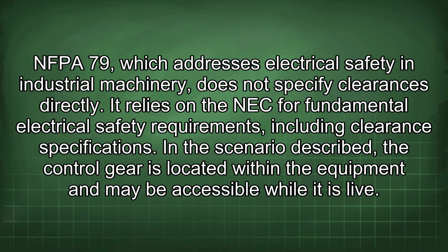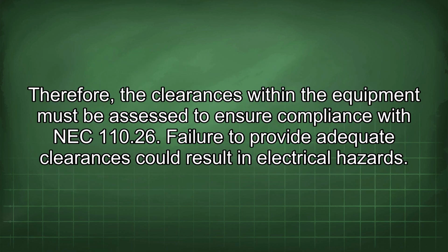NFPA 79, which addresses electrical safety in industrial machinery, does not specify clearances directly. It relies on the NEC for fundamental electrical safety requirements, including clearance specifications. In the scenario described, the control gear is located within the equipment and may be accessible while it is live. Therefore, the clearances within the equipment must be assessed to ensure compliance with NEC 110.26. Failure to provide adequate clearances could result in electrical hazards.